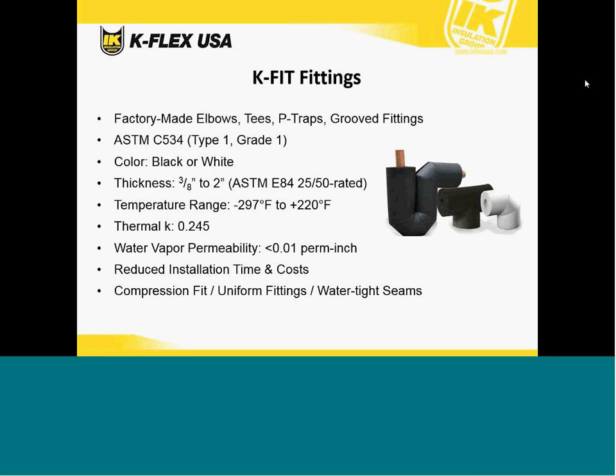We also have a line of K-Fit fittings. These are molded elbows, tees, P-traps, and grooved fittings. ASTM C534 Type 1 Grade 1. They're available in black or white with thickness from 3/8 inch up to 2 inches, all of which are 25/50 rated by E84. Same range, thermal K, and water vapor permeability as our standard product. The benefit of these fittings is that they reduce installation time and cost for the contractor in the field. They provide compression fit, uniform fittings with watertight seams that were made in a controlled environment and repeatedly made in that controlled environment. So you've got the same level of quality in the fittings that you do in the insulation material.